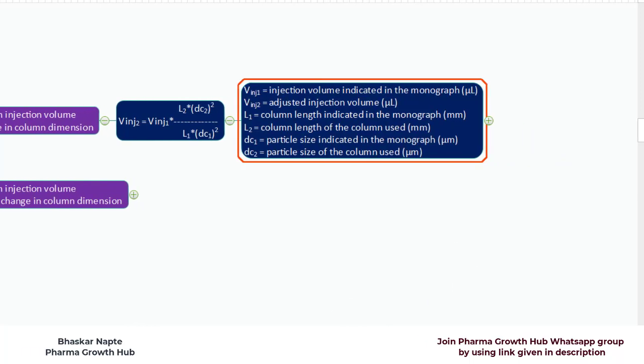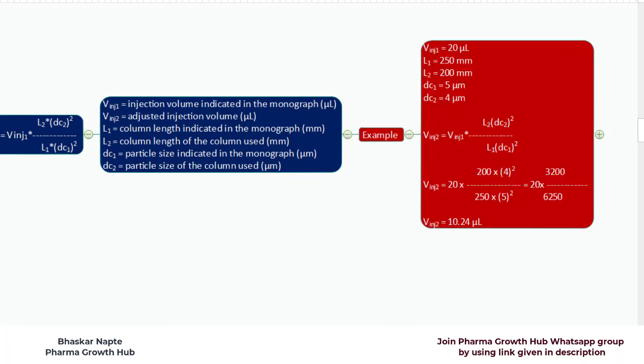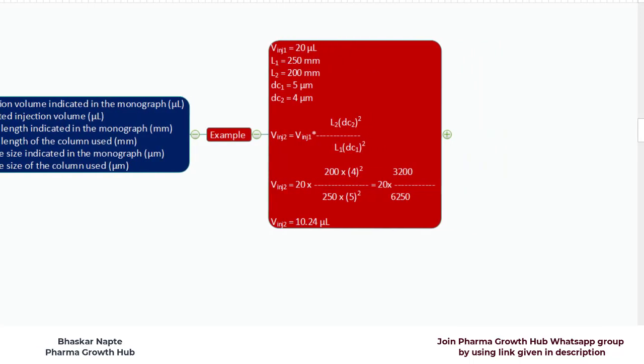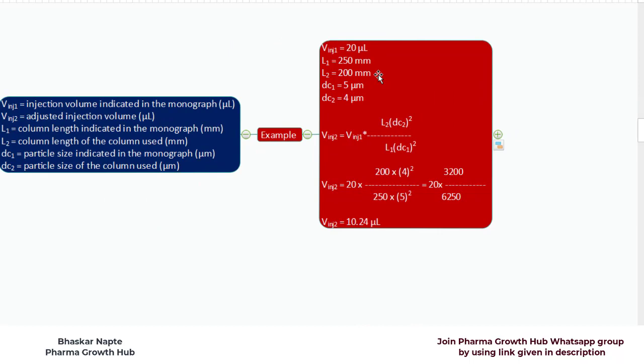Now let me explain the calculation of the injection volume with help of a very simple example. Here is the example on your screen. V injection 1, the injection volume indicated in the monograph, is 20 microlitres. The length of the column as per the monograph method is 250 mm — that is L1. L2, the length of the column you want to use, is 200 mm.